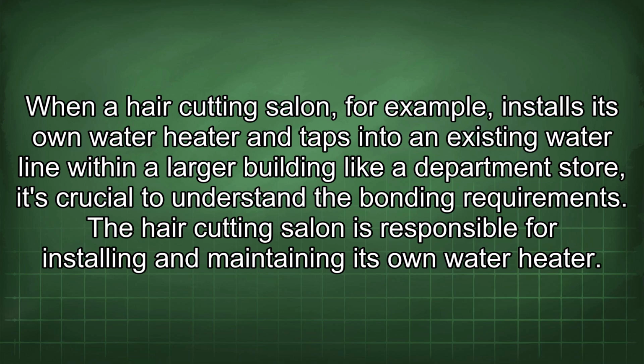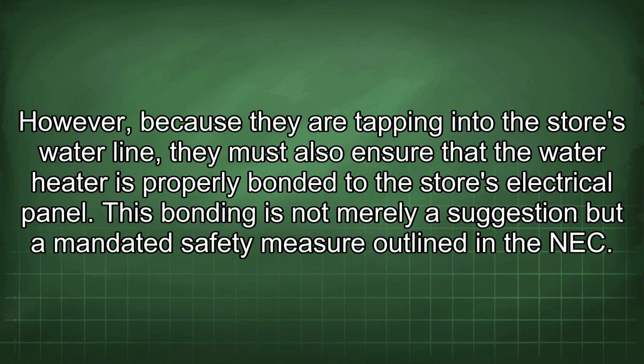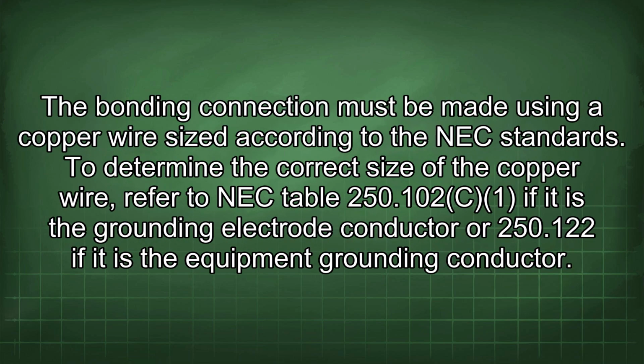The haircutting salon is responsible for installing and maintaining its own water heater. However, because they are tapping into the store's water line, they must also ensure that the water heater is properly bonded to the store's electrical panel. This bonding is not merely a suggestion, but a mandated safety measure outlined in the NEC. The bonding connection must be made using a copper wire sized according to the NEC standards.